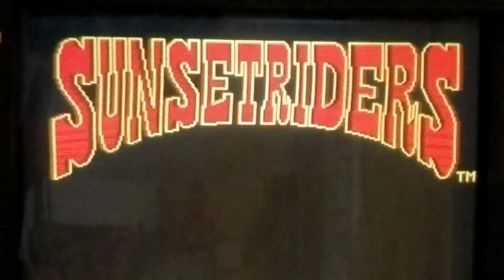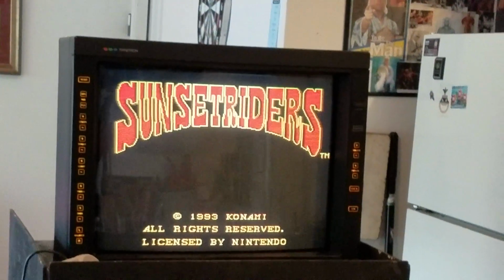Okay, there's one more quick thing you've got to check here too. I forgot to mention, there's black screen sometimes, and you might not be able to see on the camera there, but there's a white line kind of coming up above here, and I need to make sure that I vertically expand it so that's out of the picture. I don't want that to show up, even though it will take a little bit of my screen out. We're just going to go ahead and vertically expand that. Other than that, you can see our screen. She looks pretty good, and I think we're successfully done in calibrating this monitor.